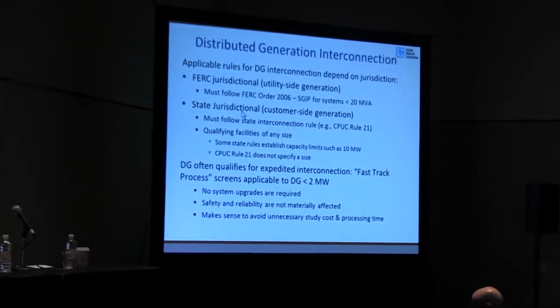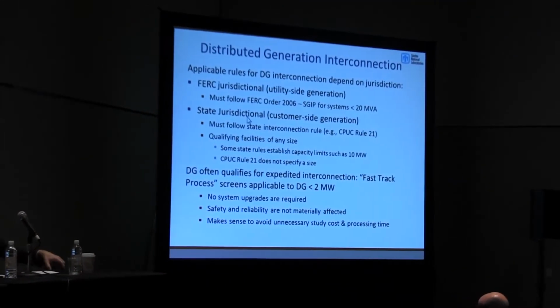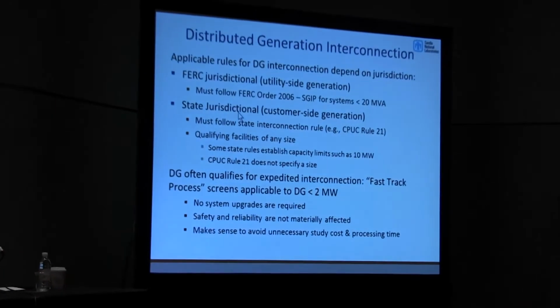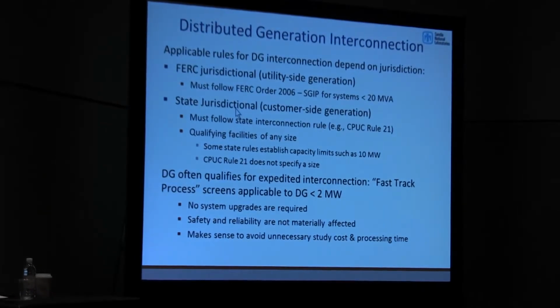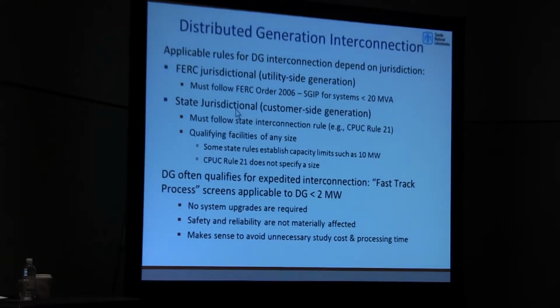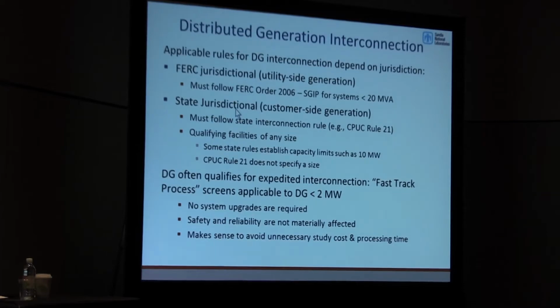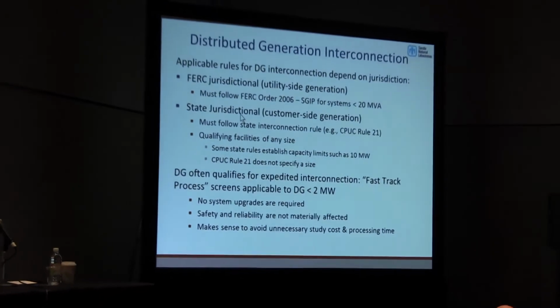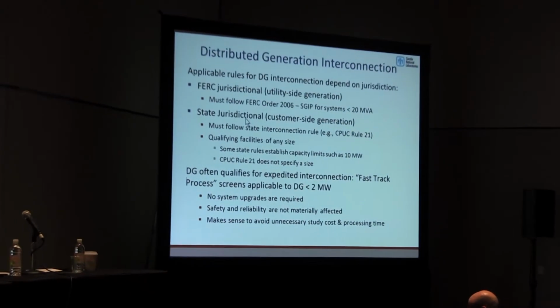So for distributed generation, in terms of the rules you have to be concerned about, there are primarily two jurisdictions. The first is the FERC jurisdiction, utility side generation. Typically this follows the SGIP process, and it's for 20 megawatts or less. The rest is covered by state jurisdiction. This is typically customer side generation. The rules vary from state to state. However, 10 megawatts is a typical upper level for what can be covered under this jurisdictional area.